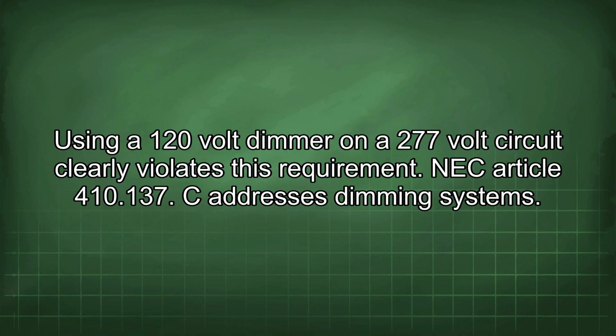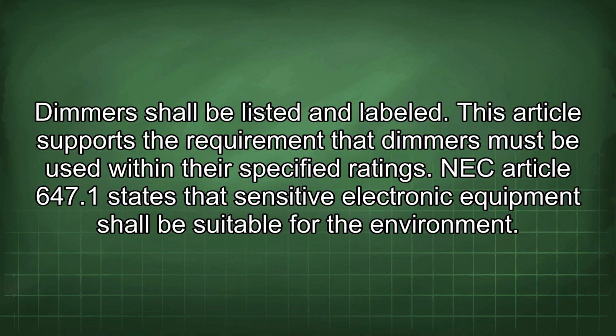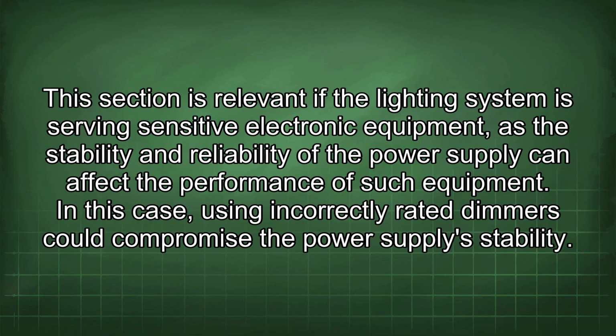NEC Article 410.137(C) addresses dimming systems. Dimmers shall be listed and labeled. This article supports the requirement that dimmers must be used within their specified ratings. NEC Article 647.1 states that sensitive electronic equipment shall be suitable for the environment. This section is relevant if the lighting system is serving sensitive electronic equipment, as the stability and reliability of the power supply can affect the performance of such equipment. In this case, using incorrectly rated dimmers could compromise the power supply's stability.